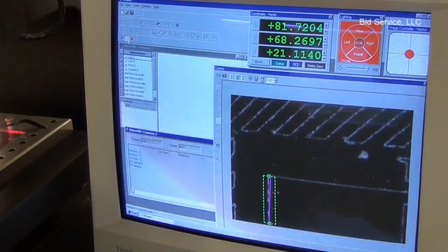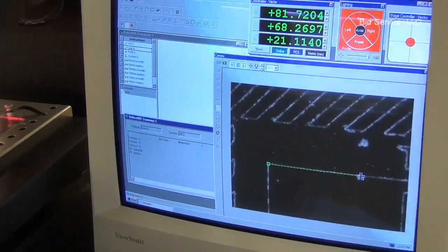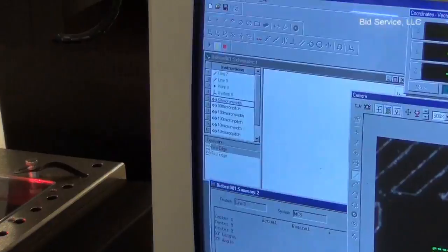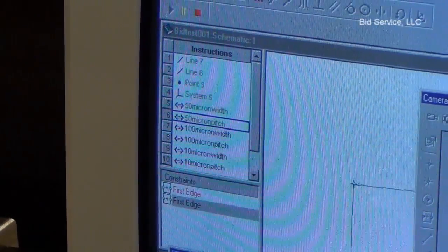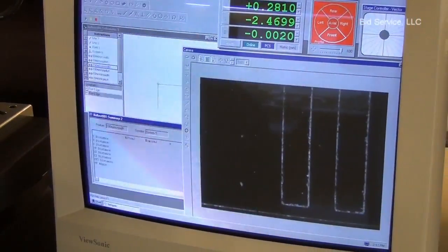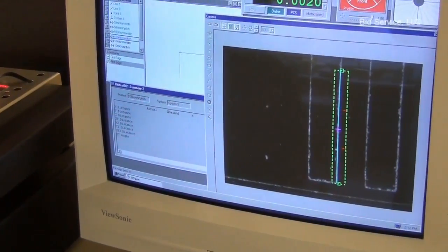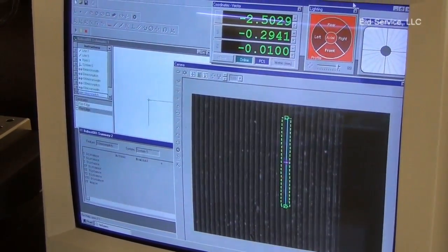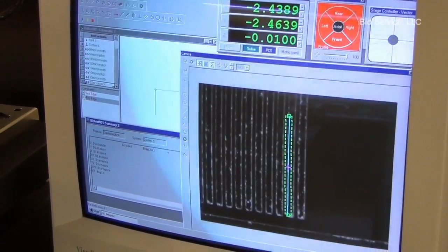Hit the yellow pause button, enter. Now it's looking for line 8. The program is running — it's looking at the width of the 50 micron, now it's going to look at the pitch, 50 micron. If you notice the stage will move slightly. We did the 100, now this is the 10 micron — pitch and width, width and pitch actually. And here's the 20.